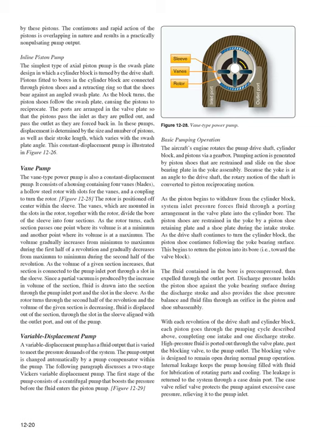A variable displacement pump has a fluid output that is varied to meet the pressure demands of the system. The pump output is changed automatically by a pump compensator within the pump. The following paragraph discusses a two-stage Vickers variable displacement pump. The first stage of the pump consists of a centrifugal pump that boosts the pressure before the fluid enters the piston pump. In Figure 12.29, the aircraft's engine rotates the pump drive shaft, cylinder block, and pistons via a gearbox.